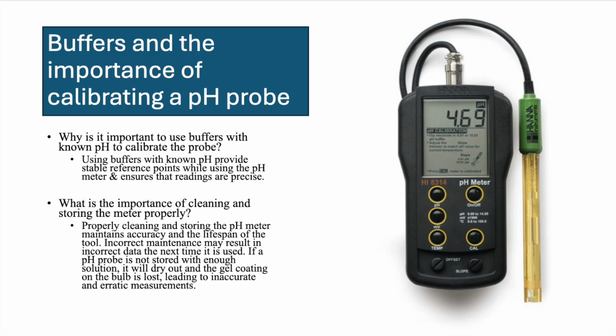Using buffers with known pH to calibrate the probe provides stable reference points while using the pH meter and ensures that readings are precise. Cleaning and storing the probe is also important. Properly cleaning and storing the pH meter maintains accuracy and the lifespan of the tool. Incorrect maintenance may result in incorrect data the next time it is used. If a pH probe is not stored with enough solution, it will dry out and the gel coating on the bulb is lost, leading to inaccurate and erratic measurements.